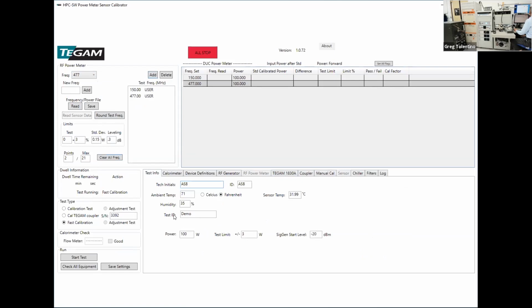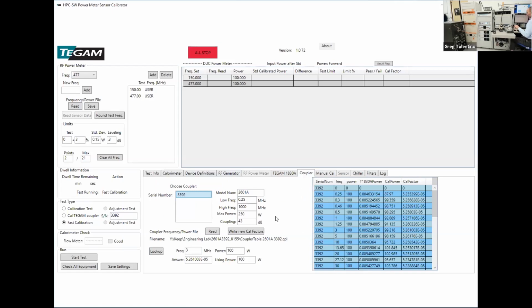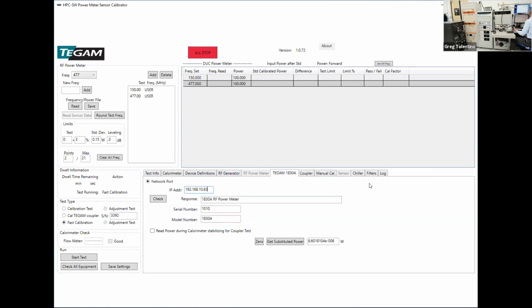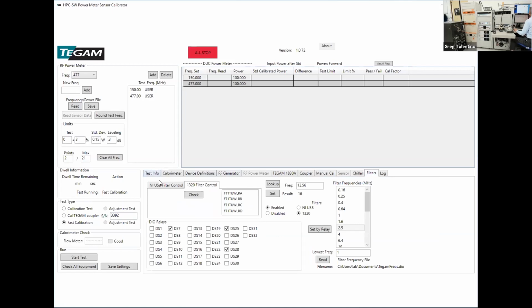So let's go back to the test info. Yeah, we're going to test it at 100 watts. We are going to use that amplifier. We have to use that amplifier. Using the same coupler, so I can use the same coupler coefficients. I'm using the same 1830A. Filters are all good. I'm not going to try to adjust that because I can't adjust it electronically. Pass criteria on the Telewave is 5%. And other than that, I think we're good to go. Let's start the test.